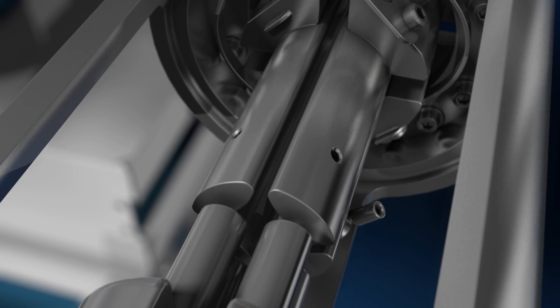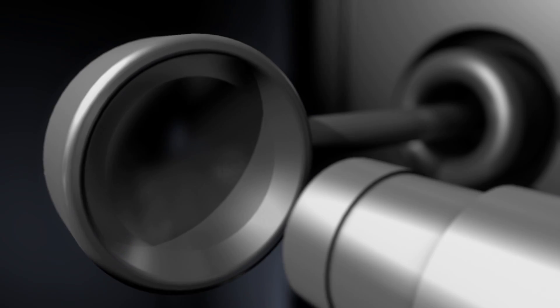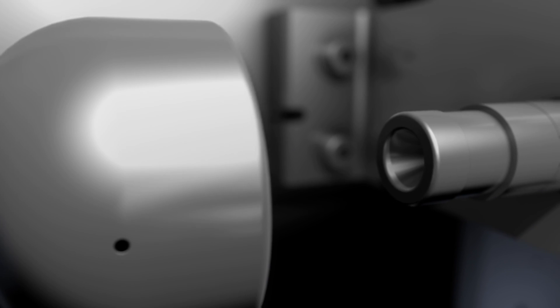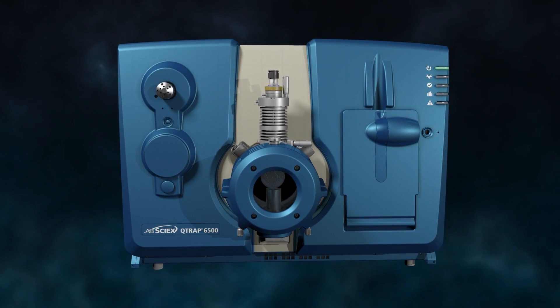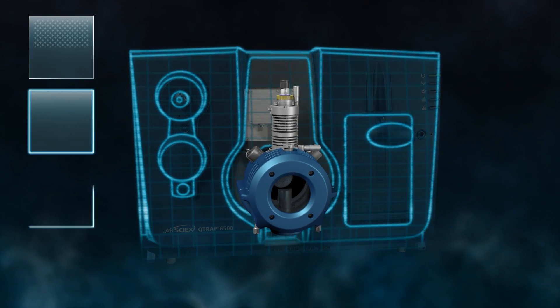The patented ion drive technology consists of system-wide technological advances that not only increase the number of ions produced in the source, but also change the way the ions are focused and detected. Ion drive technology is enabled by three major new innovations.